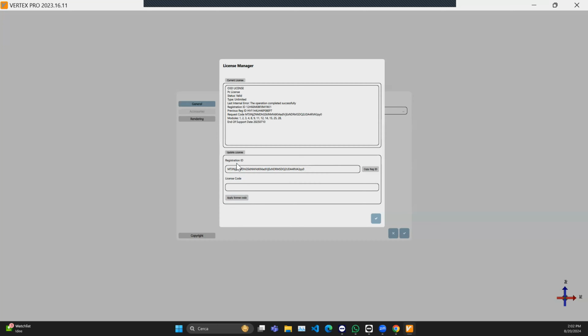It happens a few times in a year that we have to manually activate the scanner. Usually the automatic online activation works very well. The problem is sometimes that there is something installed on the computer, kind of firewall or something blocking the connection between the scanner and the remote server. If it happens, of course, the automatic activation is not working, so you need to send us that code. Or sometimes it also happens because this server is not managed by us, but it is a service provided by a supplier of ours. If there are problems on the network or on its internal network, it doesn't work.